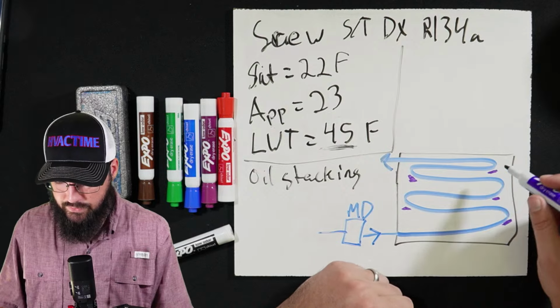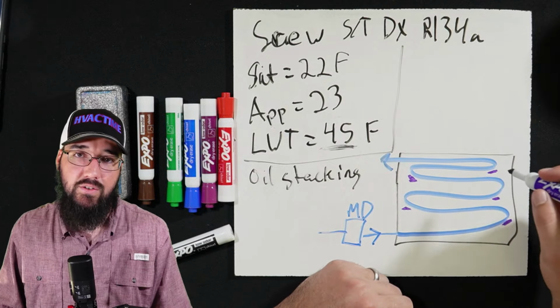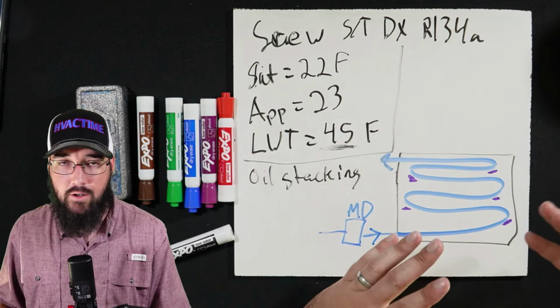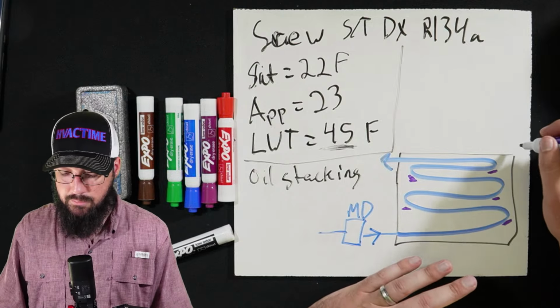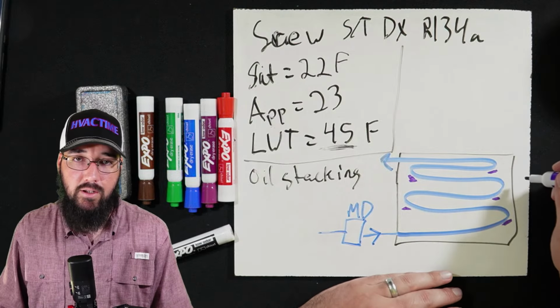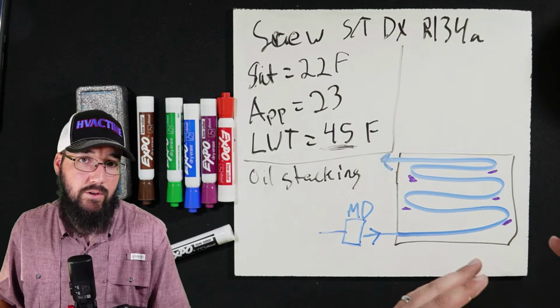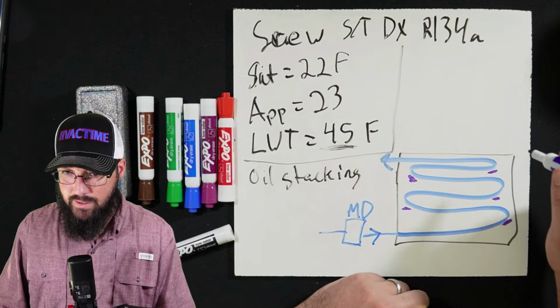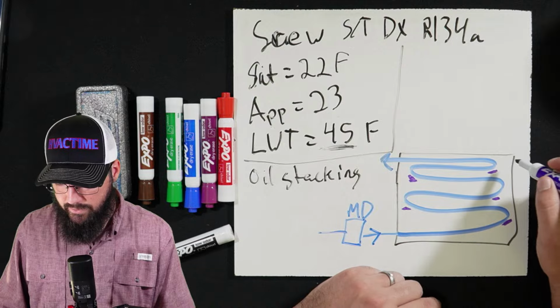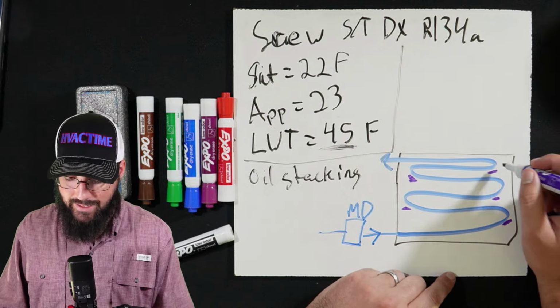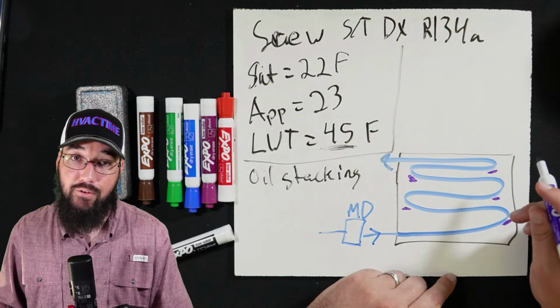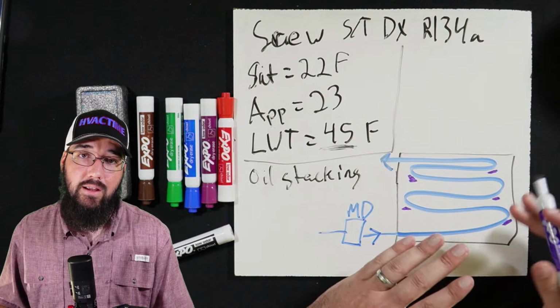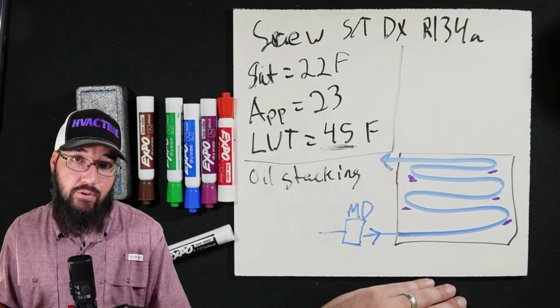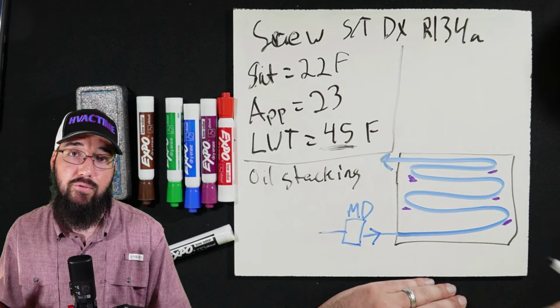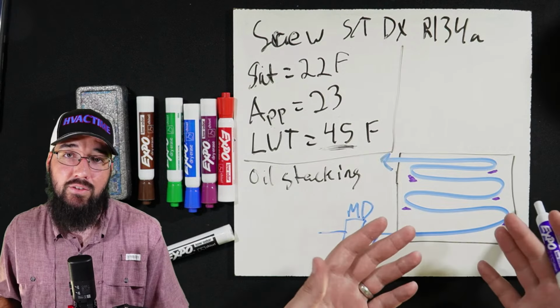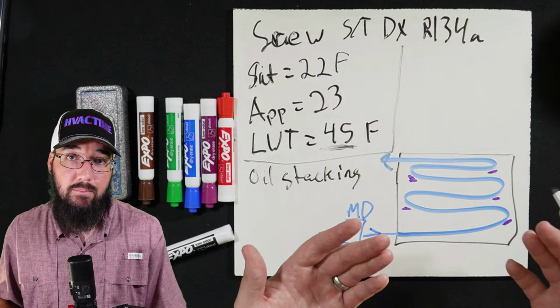And part of what you'll see in this process is, in the oil separator, not all of them have sight glasses on them, but if yours does, you'll see the oil separator levels begin to lower. That's if you can see that. In that scenario, with enough runtime, you can oil log this evaporator. The fix for this is to either increase head pressure even further, so turn off some condenser fans, force a higher velocity, or let that circuit stage up, which is the best thing to do.